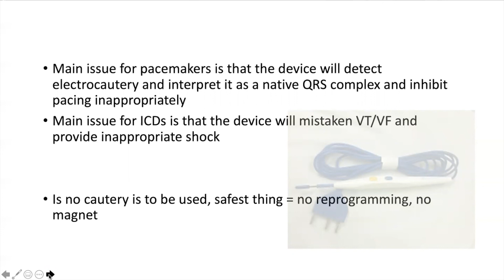If you're called to the OR and they're going to use cautery, and the patient has a pacemaker and is pacemaker dependent, you want to place or tape a magnet over the device. The magnet will put the patient in DOO or VOO if they have 2 leads, or VOO if 1 lead. That means the patient will pace the A and the V, or pace the V, without sensing anything. It's going to be in an asynchronous mode. And this works well in 95% of the cases.